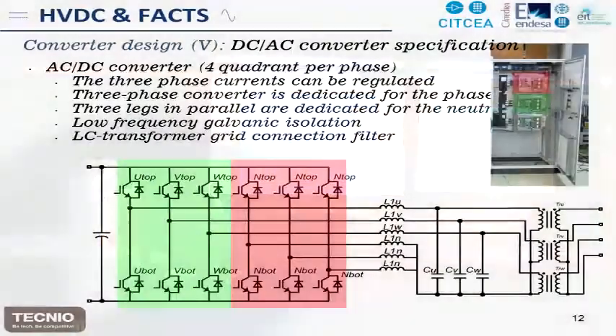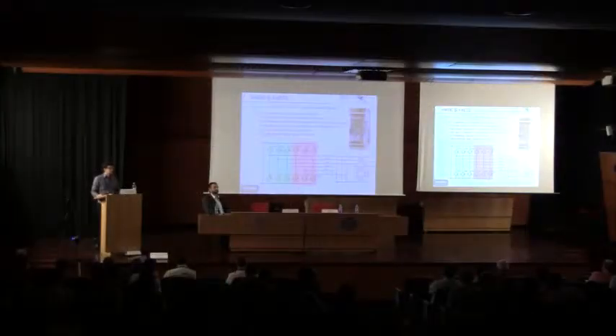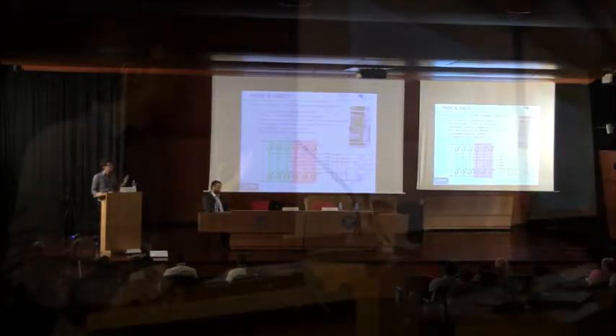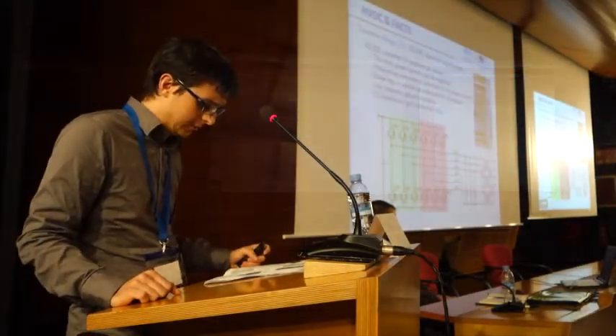For the DC-AC converter specification, as I have said before, the idea is to try to operate with a 4-quadrant PQ system per phase. This means that we are proposing to use a 6-leg converter where 3 legs are used for each active phase and 3 more legs are used only for the neutral wire. Why is this needed? Because there can be the casuistry that, depending on the active and reactive reference that the system receives, the currents can be in phase, and this means that all the current will return through the neutral. And if we want to control the neutral and have this 4-quadrant per phase system, we need to triplicate that converter if we are using the same modules. Obviously, if we are using different modules, you can avoid triplicating the number of semiconductors.